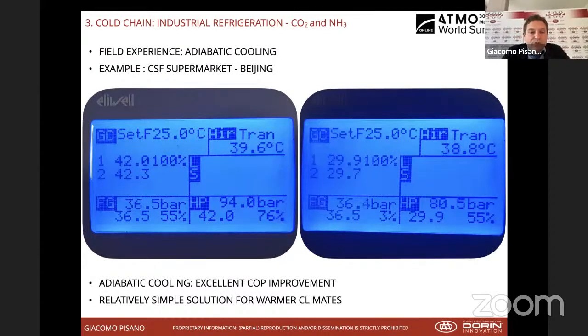Actually, adiabatic cooling works very well with carbon dioxide. From this one slide, you can see field measurement of an adiabatic gas cooler working in Beijing. This is an example from a large supermarket in Beijing, a transcritical unit. For the first week of operation, the supermarket was not working with the adiabatic pads engaged for technical reasons.